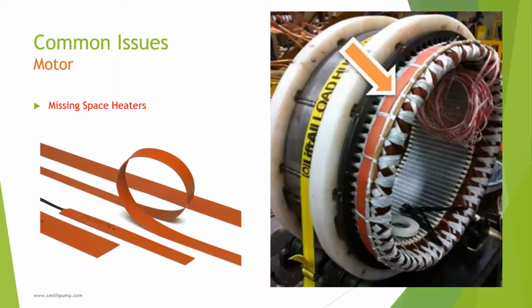And we recommend space heaters to be used on every motor sold. It's inexpensive insurance for a long-lasting motor. Space heaters, or anti-condensation heaters, are installed to prevent moisture condensation within a motor. They're typically energized while the motor is in storage or when the pump's not running. They work by keeping the internal temperature of the motor above the ambient dew point. They typically run on 120 volt power and are sized by the manufacturer according to the motor mass. You can check if a motor is using a space heater by feeling the outside housing with your hand. It should be warm to the touch, but not hot. Testing space heater function on motors is an experiment I recommend you try next time you're at the job site.